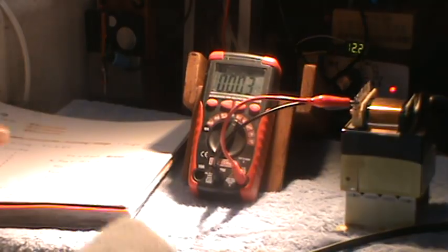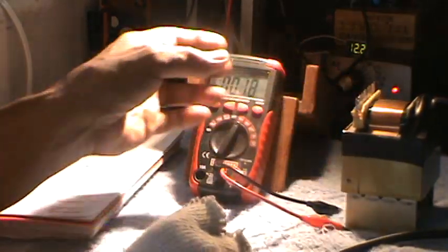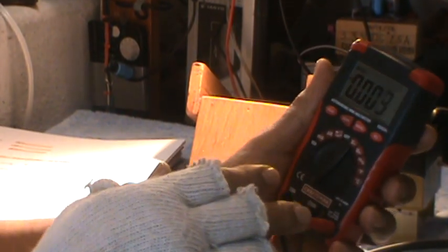So what I did, guys, is that since this transformer here has 10 terminals on the secondary, as an electrical engineer, for us to bring out the voltage to a two terminal, there should be continuity. And I measured the continuity of the individual terminals by using a multitester. I set it to the ohms setting.